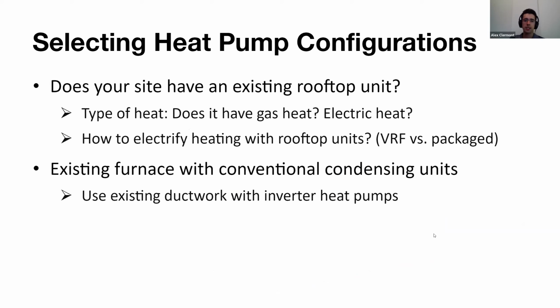So now we're going to be looking at some application considerations. So let's say you have an existing building that does have an existing rooftop unit. A question to ask would be, what is the current type of heating? Does it actually have gas heat? If so, and it's nearing the end of its life, how do you actually electrify that heating? As we previously mentioned, you can use a packaged air source heat pump rooftop unit. But remember, I mentioned they don't actually work down to very low temperatures. So oftentimes you do need backup heating in our climates.